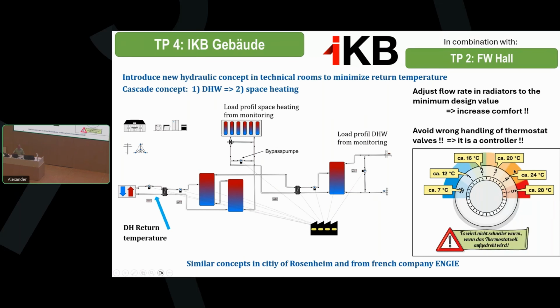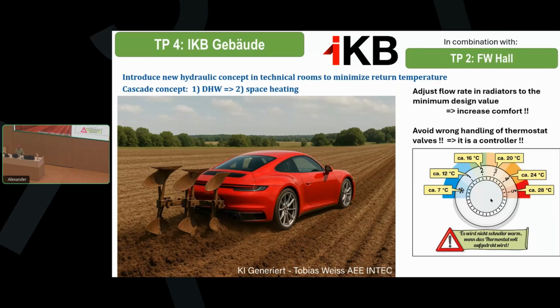That's the set temperature. And then the valve itself is a controller. It controls the power of the radiator to reach these 20 degrees. So there's absolutely no need to go to 5 and then to 1 each time. And this makes the whole system very unstable and causes big problems. In the end, that's what we very often have in heating systems: an extremely bad situation. We have a lot of power. We have high power boilers, heat pumps, district heating stations. We have high power radiators or floor heating systems, but in the end, we would not need them.